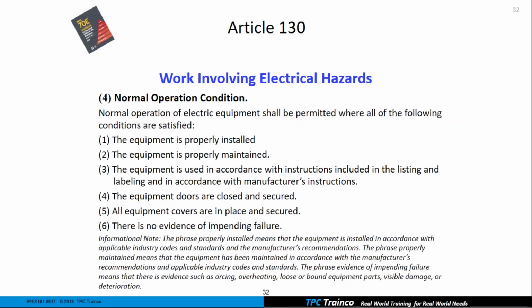4, 5, and 6 are not new. They were all there in 2015. But these are the 6 conditions that we would have to satisfy to go up and operate a piece of equipment normally, just the way the manufacturer wants us to. We shouldn't have to be wearing any PPE during this time because there should be no opportunity of shock, arc flash, arc blast. All the covers are on. The equipment's working great. Of course, if you walked up to a piece of equipment and you could tell immediately by looking at it that it has arced before, or that there are screws missing in the cover, which is not maintained properly, then we should be putting our personal protective equipment on to service that equipment.